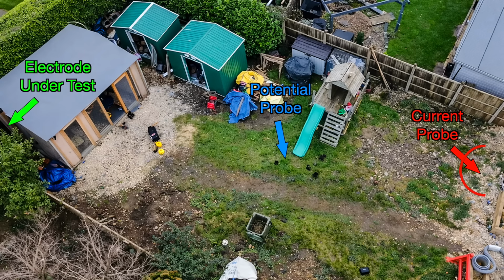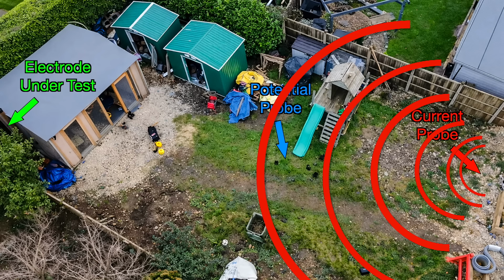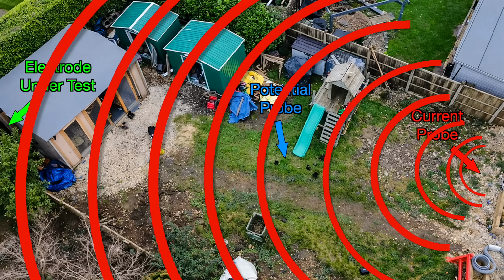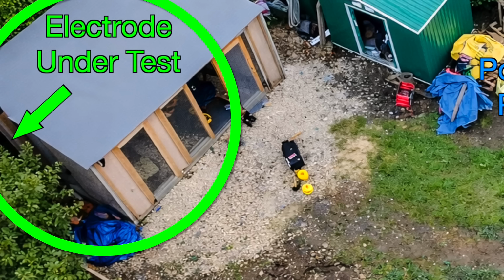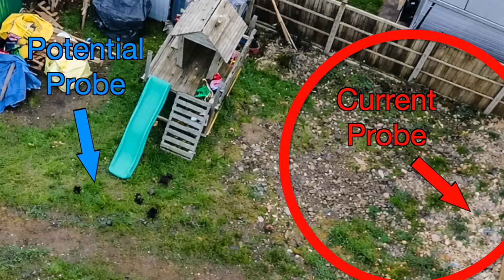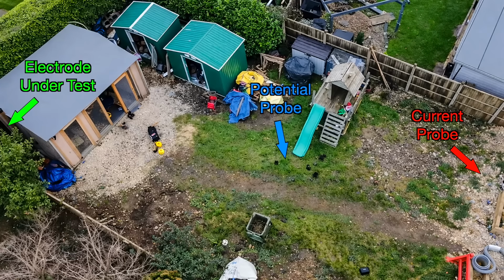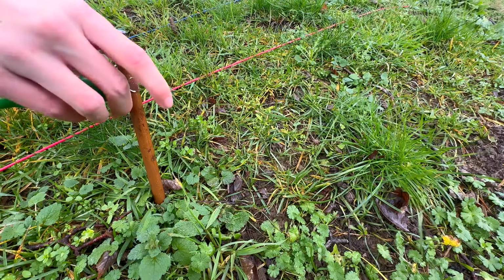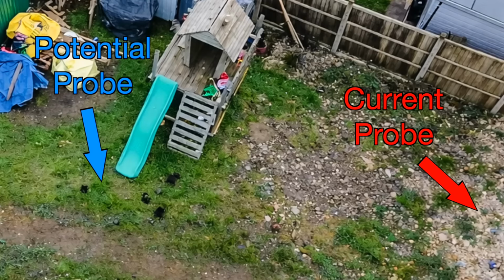Well, when we inject current into the ground, it does not travel in a straight line. It spreads out through the soil. That creates an area of influence around the earth electrode under test, and it also creates an area of influence around the current probe. If we place the potential probe too close to either of those, the readings will be affected. We are no longer measuring just the electrode. We are measuring the interaction between the two.